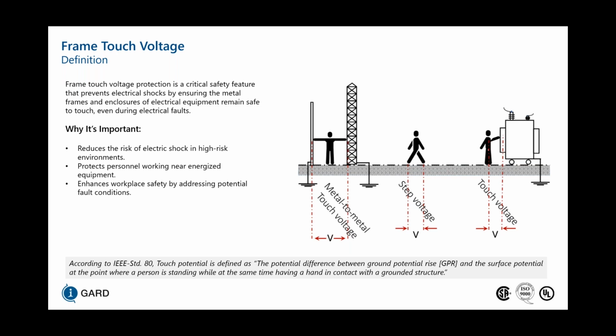with a grounded structure. So you could see the image on the right where the person is touching between two metal to metal structures, each that are separately grounded. That's a touch voltage. And in addition to that, you would also see touch voltage when touching an electrical equipment that is grounded. Now, why is it important to have frame touch voltage protection?